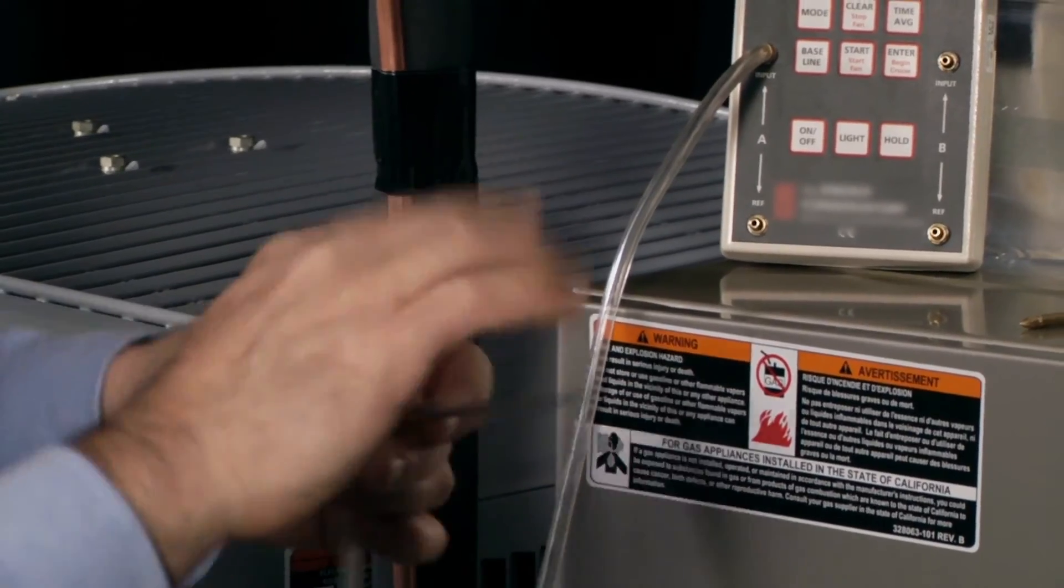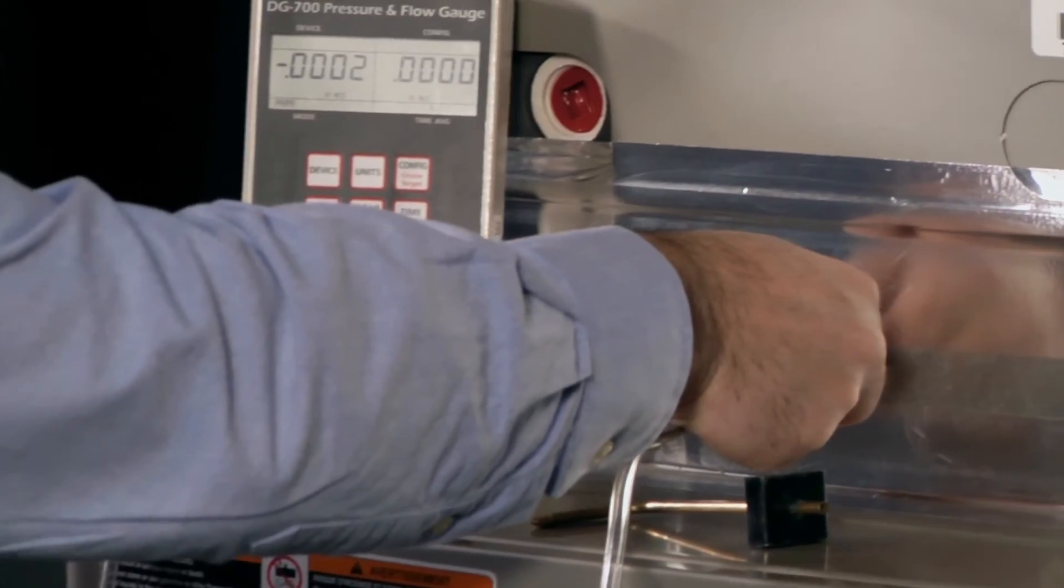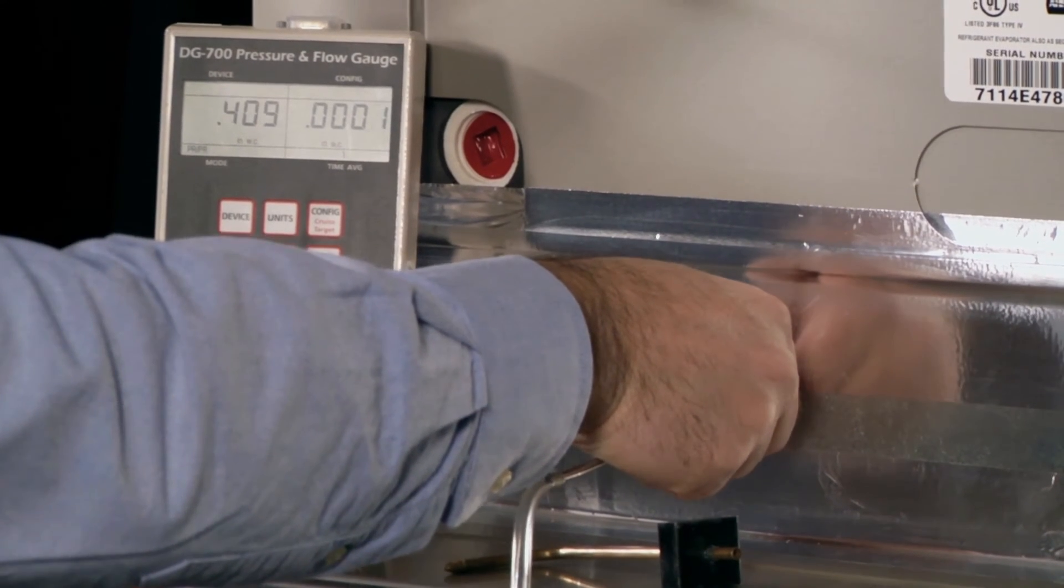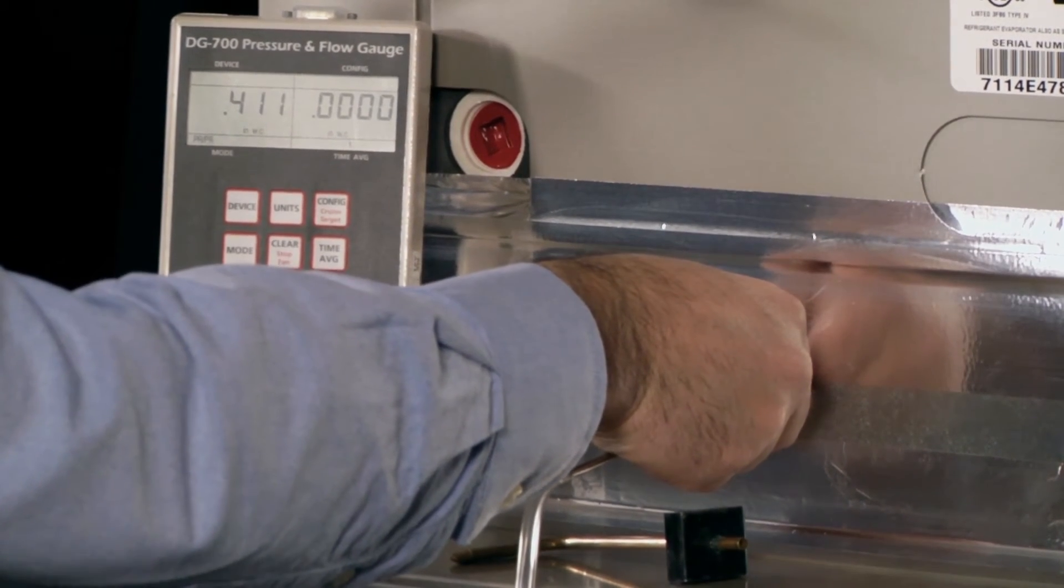Now, James is going to repeat the test using the straight static pressure probe in the same location. You can see that he gets about the same result, slightly higher than 0.4 inches water column. So you can see that whether he uses a straight or a 90 degree probe, he gets basically the same result. That's also good news.